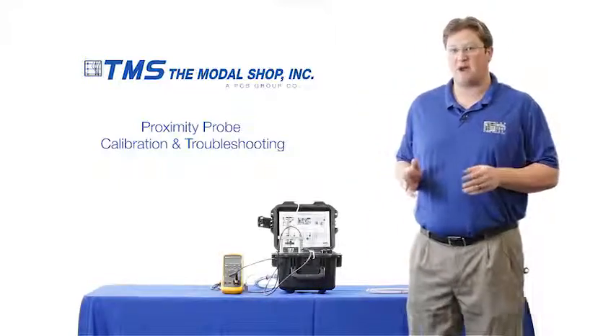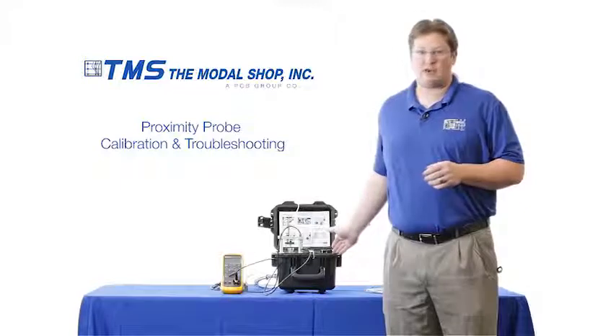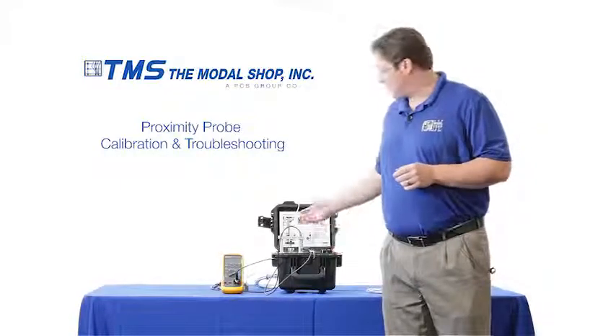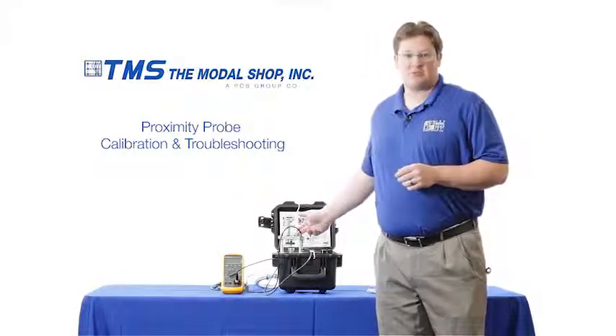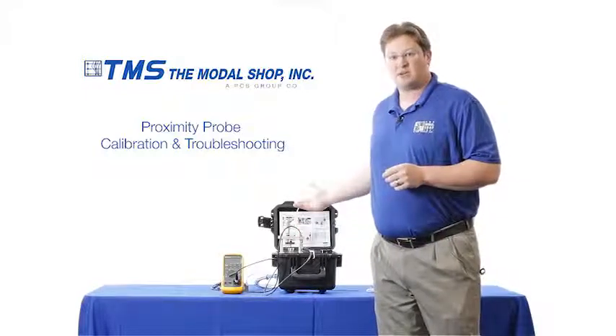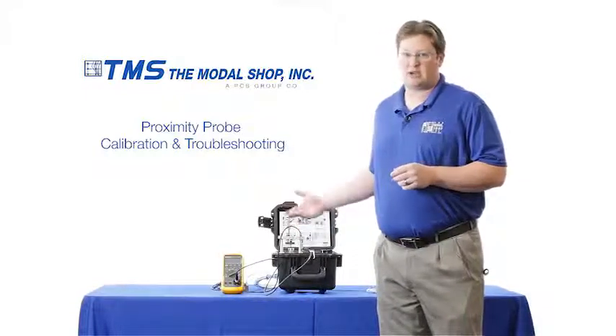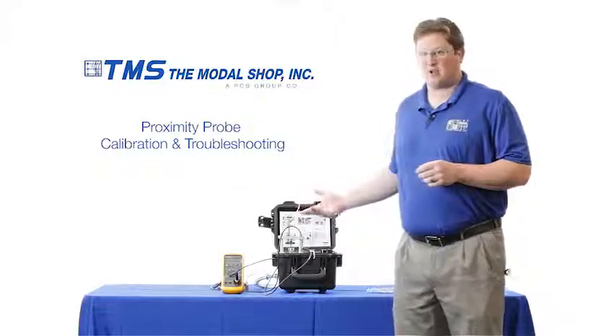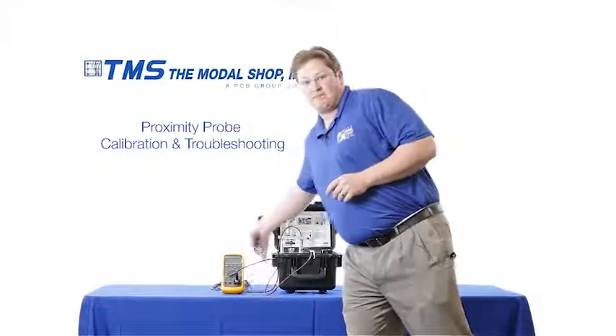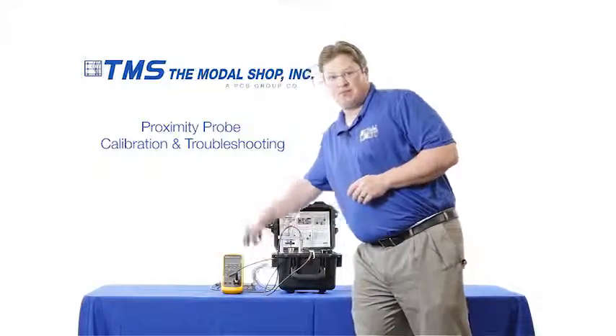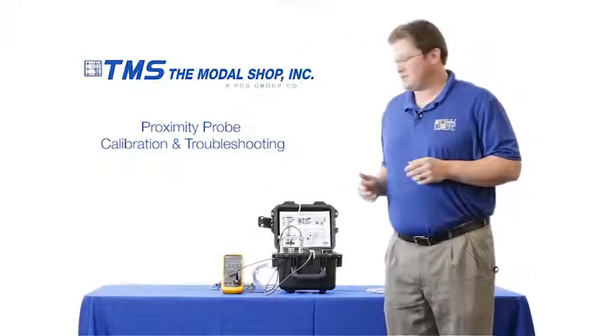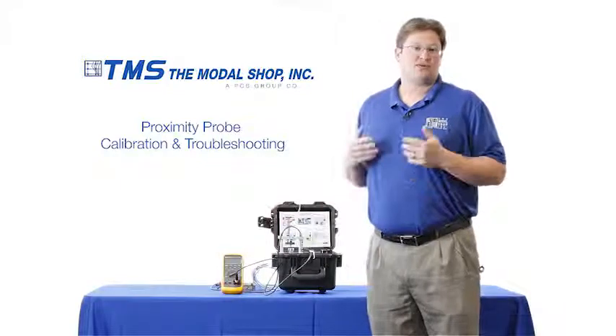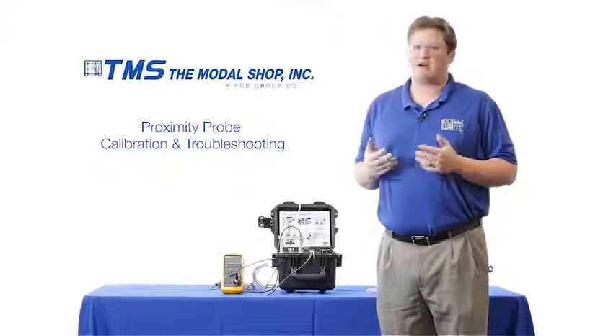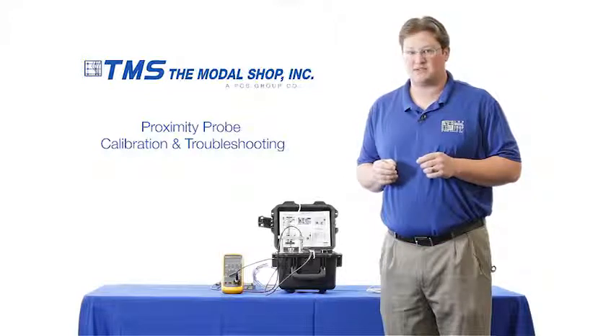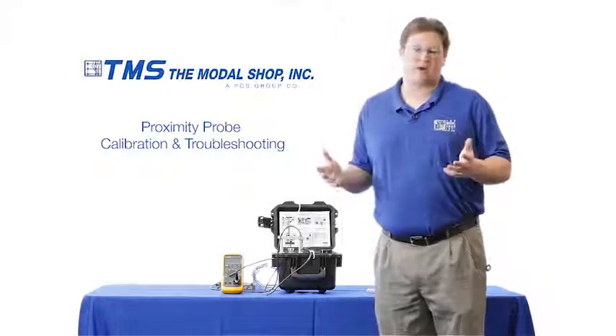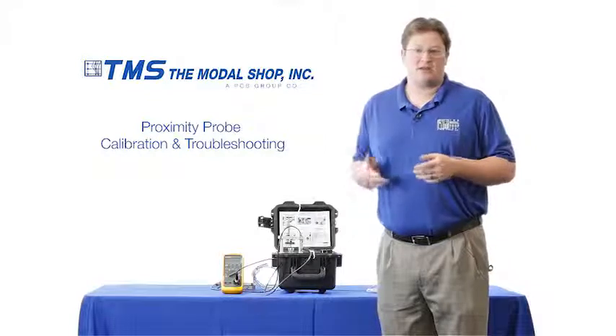In our test setup, I have our Model 9110 portable vibration calibrator. I've also mounted a proximity probe inside of our proximity probe mounting adapter. My proximity probe is a 5-meter system with 1 meter of integral cable and 4 meters of extension cable located back here. And I also have my proximeter. In this demonstration, I'll be using this digital voltmeter to essentially simulate the gap voltage button that you might find on the front of your data acquisition system. But the digital voltmeter is not required for practical use of the product in the field.